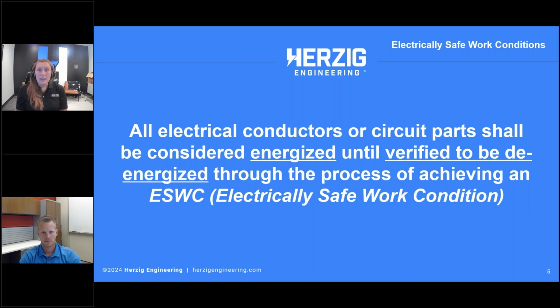In other words, unless you can complete the steps outlined in the 70E, you have to act like it's energized work. All right, so you have to keep your PPE on, you have to have the boundaries set up, you may have to have a second person depending on the task and your company's policies. There's all sorts of things that could be at play, potentially even an energized work permit if you're servicing it without verifying that it's off. Don't want to have to go down that rabbit hole for the vast majority of tasks you do. So let's just break down how we actually get it in a safe work condition and can work without all those extra hoops.